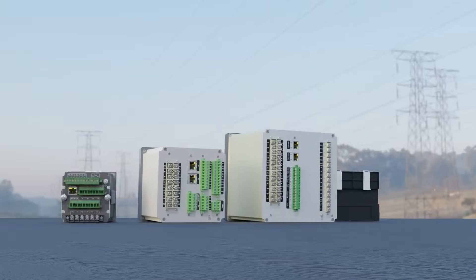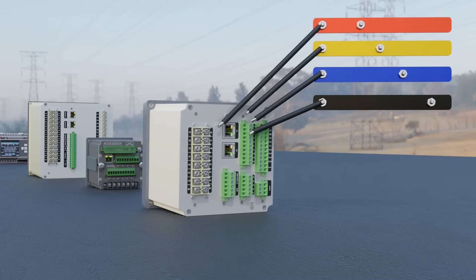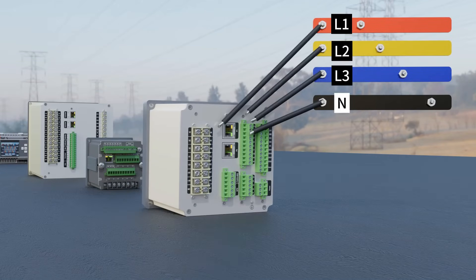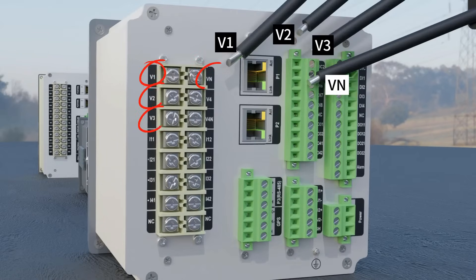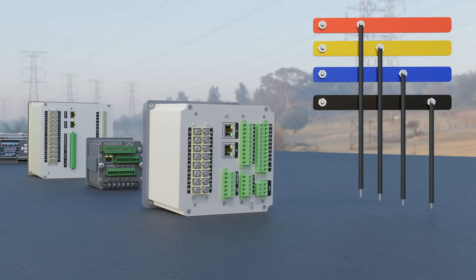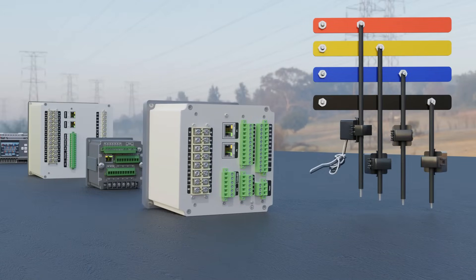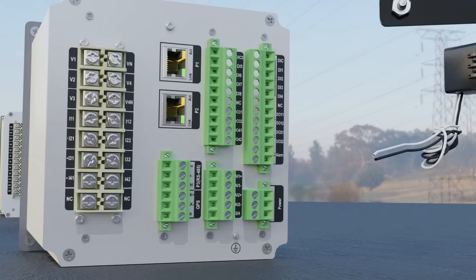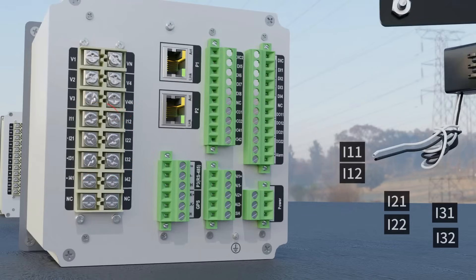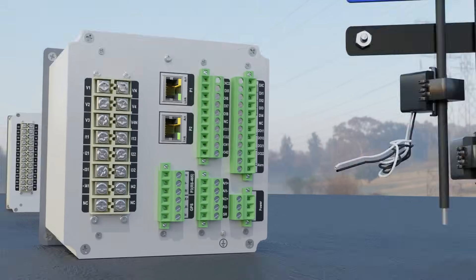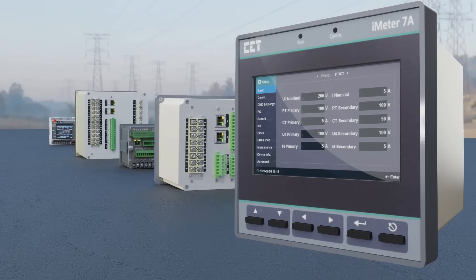Connecting the voltage source to iMeter is straightforward. Just connect line one, line two, line three, and neutral to the correspondent voltage terminals on iMeter. For current measurement, you need a current transformer CT on each power line, and the output of the CTs should be connected to the correspondent current terminals on iMeter. Finally, configure the PT ratio and CT ratio under the iMeter setup menu, and you are done.